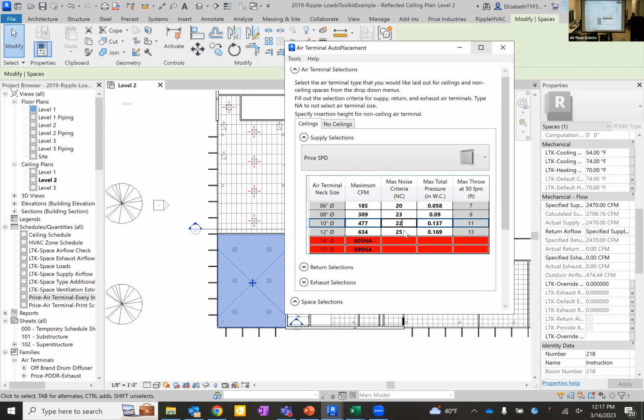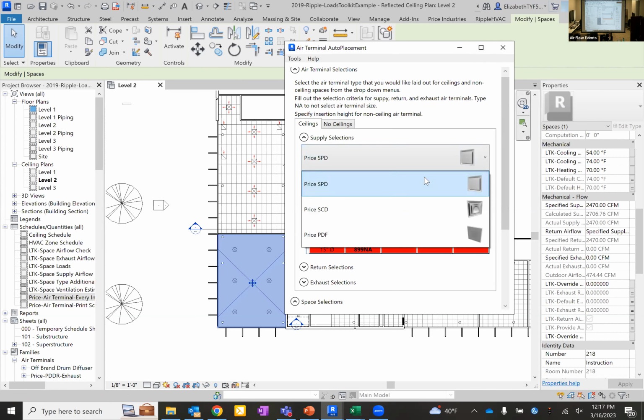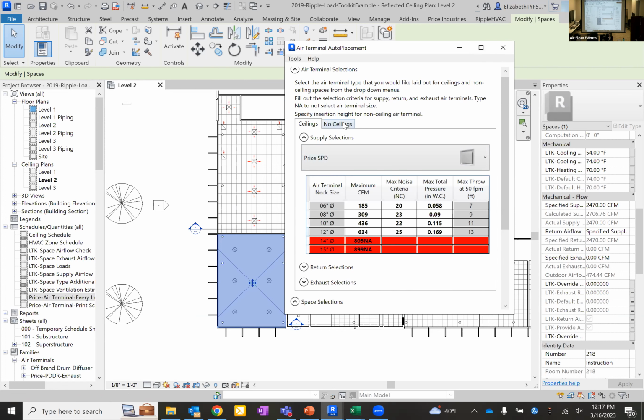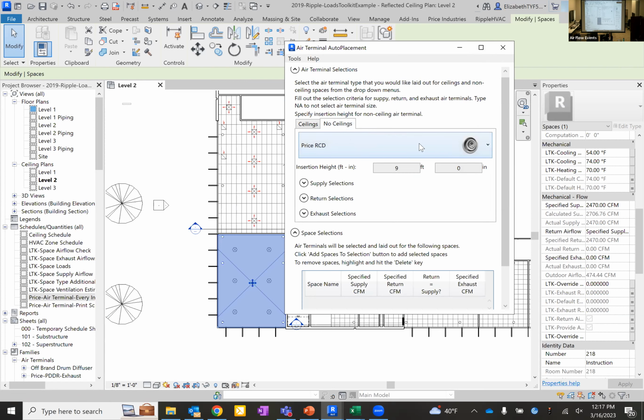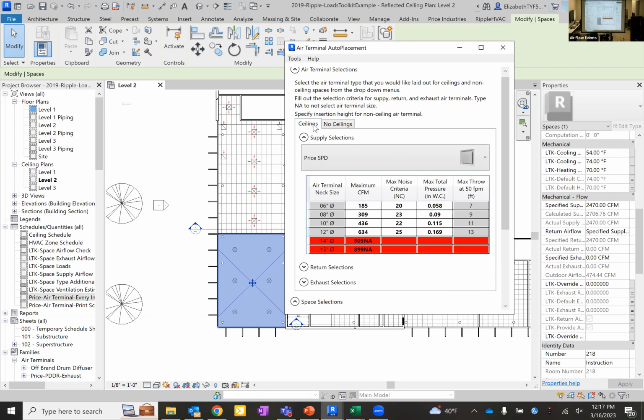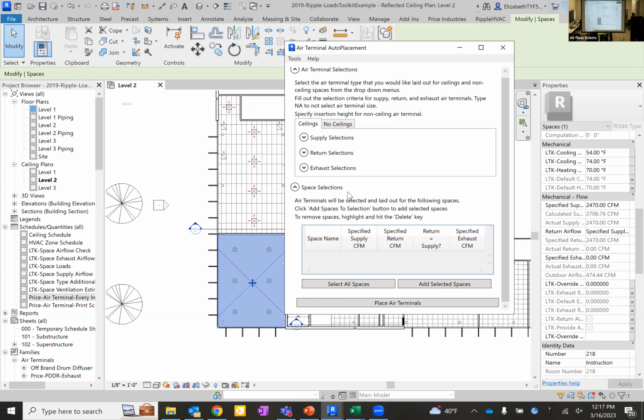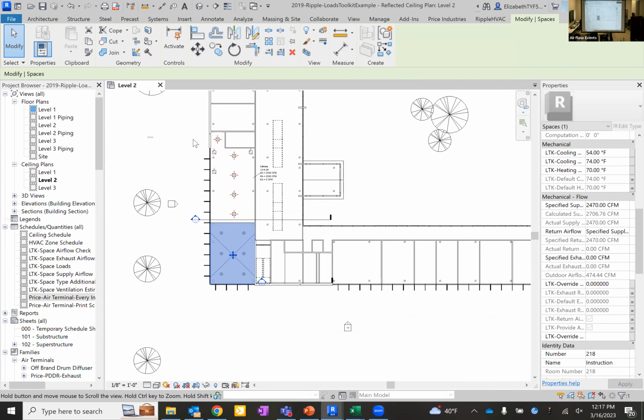I can set that as a requirement and it will set the resulting airflows. So you have the ability to set up the parameters for the placement. And then you can also choose the model type: square plaque, square cone, or perf. If we have a ceiling. If there's no ceiling, it's going to default to the round cone because that's all that's in there right now. And we can set the height of where that diffuser will land in the space. So you can set all these predefined parameters and then the selection tool will run based off of those.